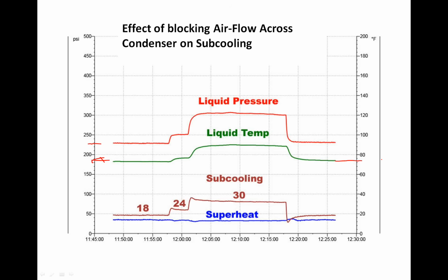The liquid temperature, again, here's the highest it got. Whoops, sorry, straight across there. Trying to run this mouse is tricky sometimes. You know, it only went up, from 77, this is 80, 85, 90, it only went up a few degrees. The pressure went way up there. So what happened was the condenser is so oversized on this high efficiency system that the pressure goes way up, but the liquid's still able to maintain very reasonable temperature ranges. And what's happening is we're artificially raising the subcooling, okay? So we're raising the saturation pressure without changing the liquid temperature very much, changing the design characteristics of the condenser. So we really weren't, because you can see the superheat remained constant, we weren't changing the level of refrigerant in the coil, we're changing the way the thing operated.